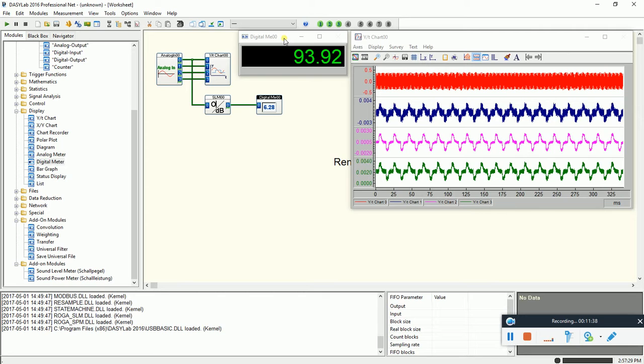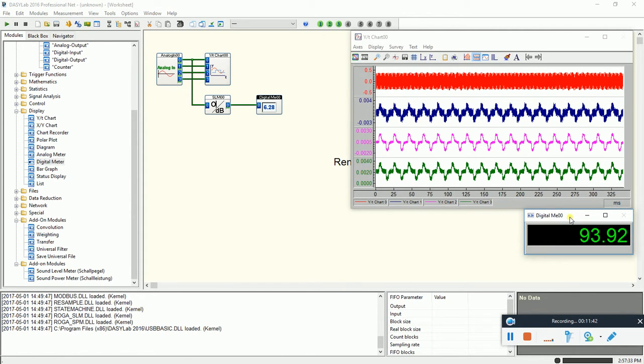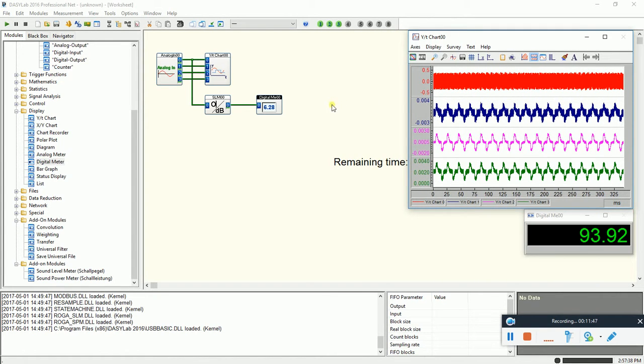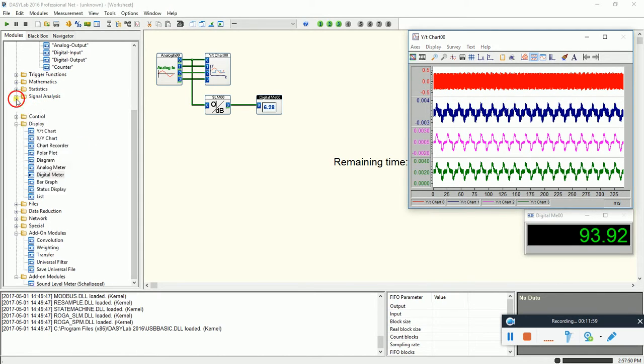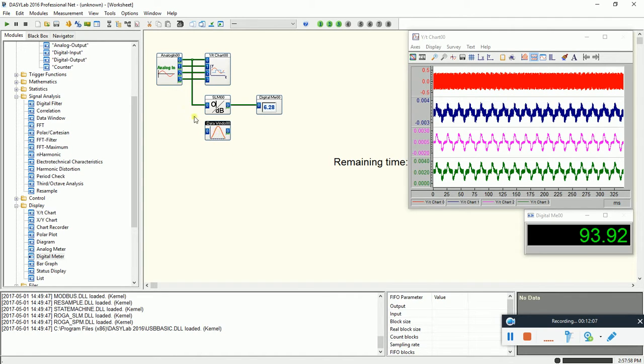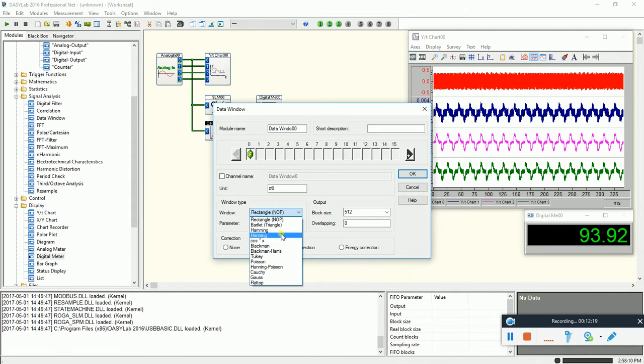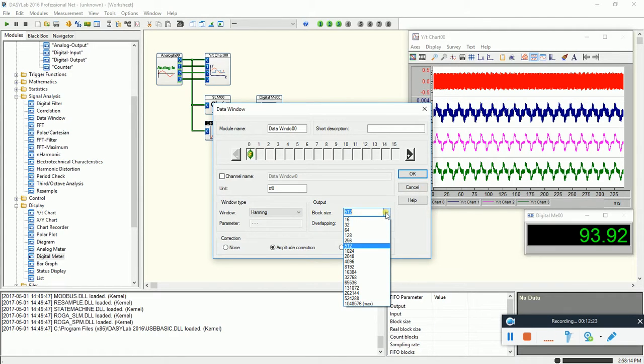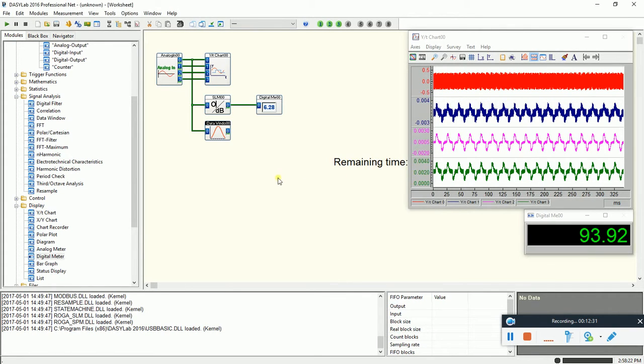Then as next I like to show you how to make a FFT. So in this case I take this signal. So means I take here the signal analysis. So as first I take here the data window. Now I get here the signal from channel from my microphone. Here I adjust the Hanning window and the FFT resolution, let's say is 8192 FFT lines. So next I take the FFT.